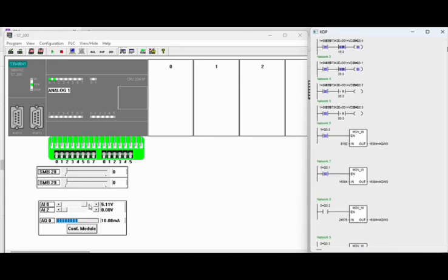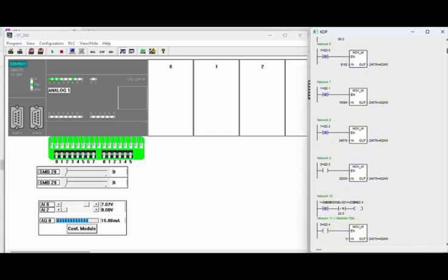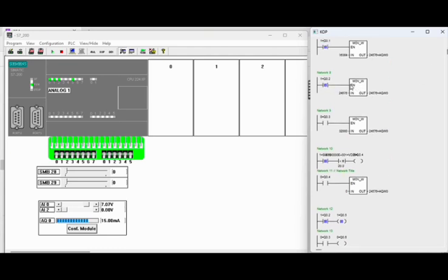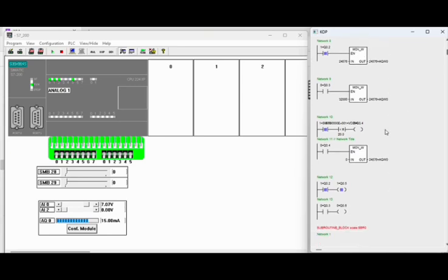And then as water continues to rise inside the water tank, the radar sensor has a 15 milliampere reading, signaling high level on the water tank, thus turning on the high level indicator light on this part. High level indicator is turned on, which triggers pump number 1 to be turned on since the water is now at high level.